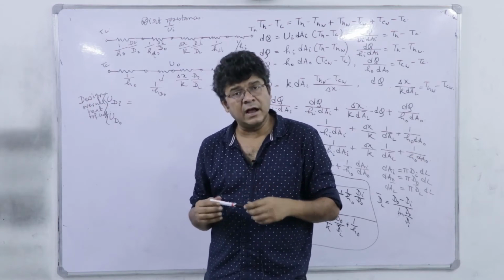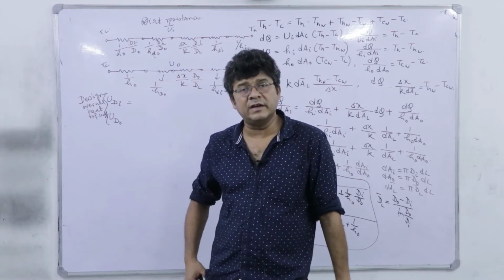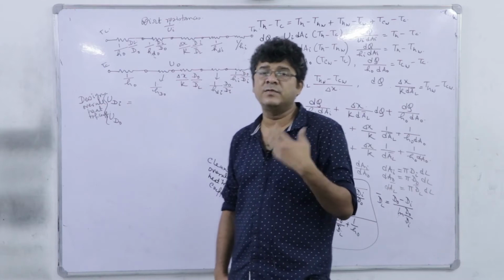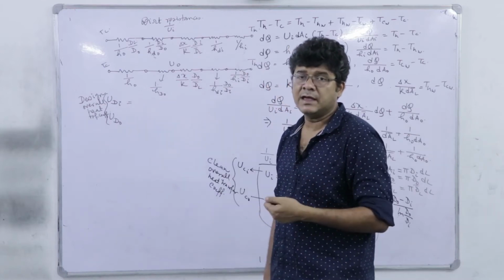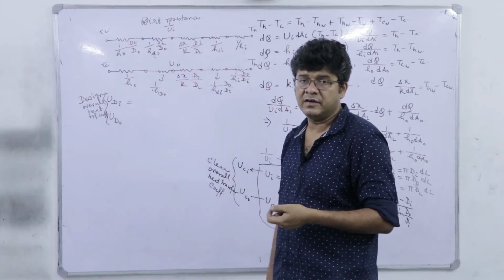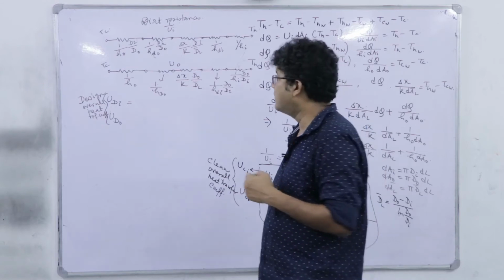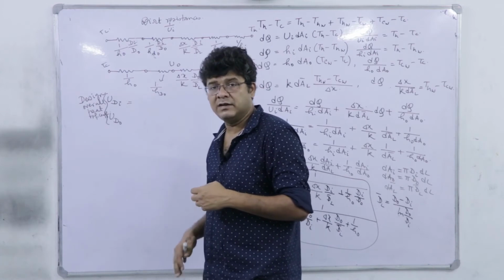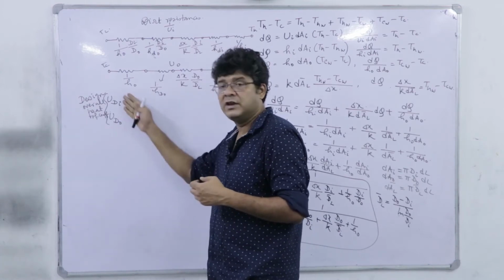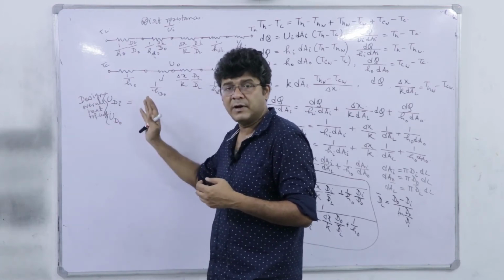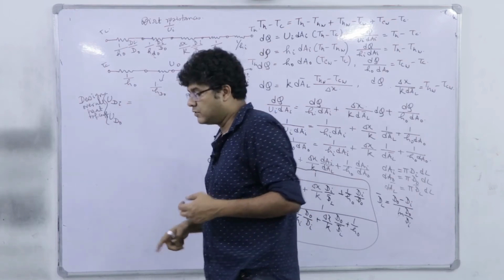So when we include the projected or tentative dirt resistance with a factor of safety in my calculation of heat exchanger area, then the corresponding heat transfer coefficient must be referred to as design overall heat transfer coefficient, because we have to do the design of shell and tube or double pipe heat exchanger with these values, not with clean overall heat transfer coefficient.